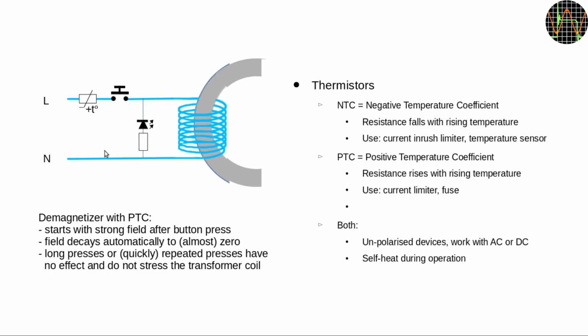Since it can only go up to a finite resistance, there will always be a little current flow, so the magnetic field doesn't decay all the way to zero, but it's close enough. Long button presses or repeated presses in quick succession keep the PTC hot and therefore have no effect. You have to wait for it to cool down about half a minute or so before you have another go.